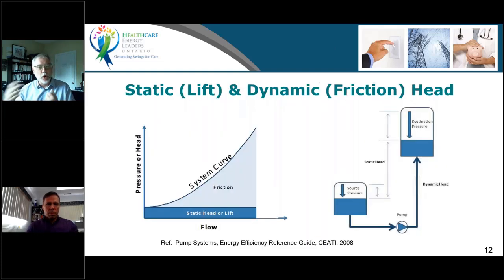But when it comes to an open system, say we're moving water up to a cooling tower, that system is open because we don't have the benefit of the water coming back to give us back the head or the rise in height. At that point, no matter what the flow is, even at zero flow, there's a head difference or a pressure difference between the source and the destination. So ultimately, the system curve doesn't come back to the zero point on the pressure-flow relationship.